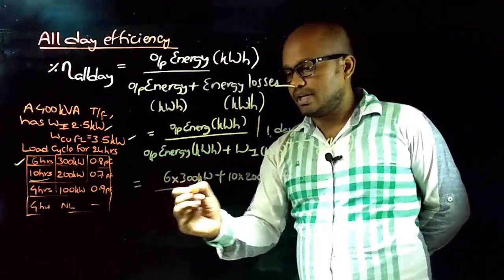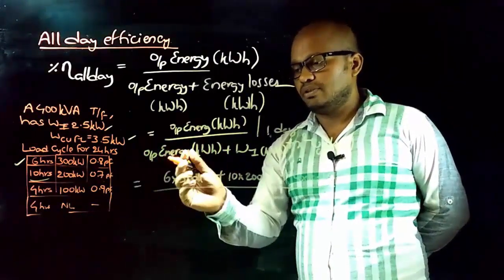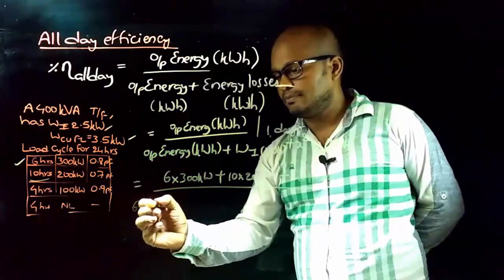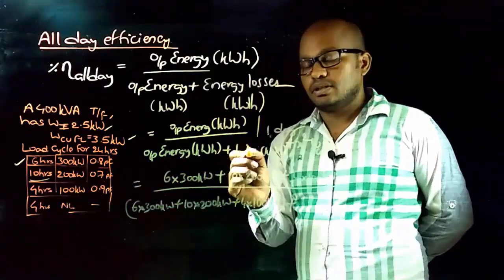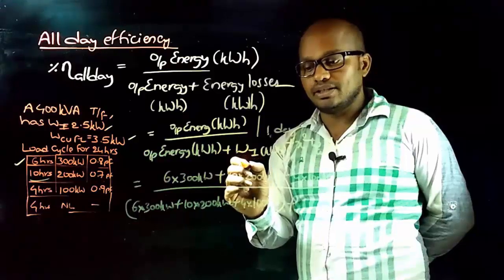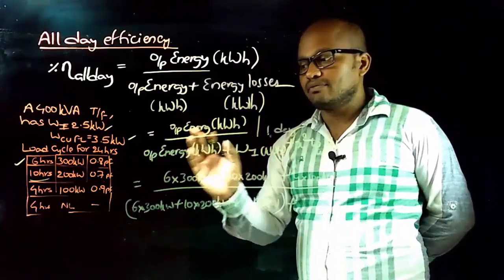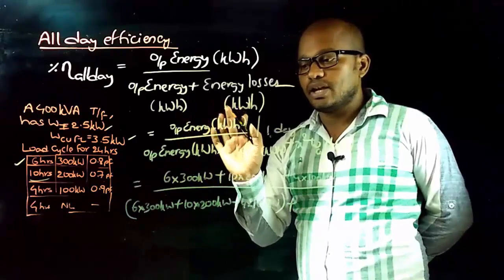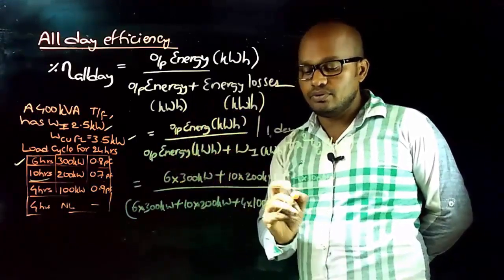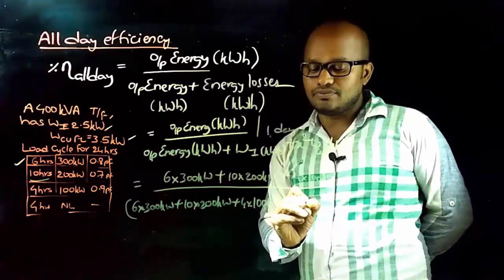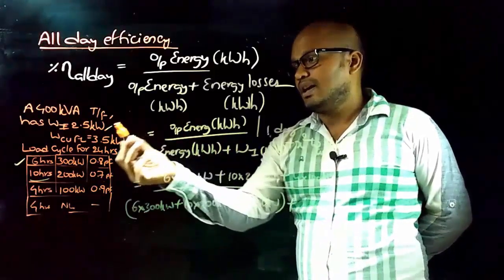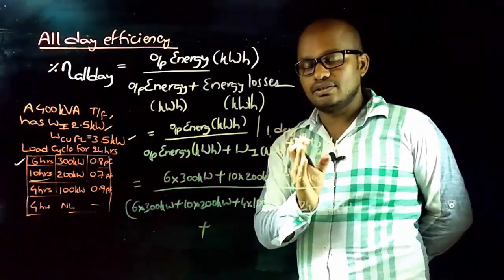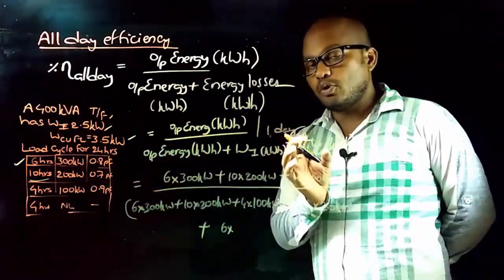This total output energy is divided by the same output energy plus the energy losses. An important point to keep in mind: iron losses are present for the whole 24 hours whether the transformer is loaded or not. So you must include 24 × 2.5 kilowatts for iron losses in the denominator.